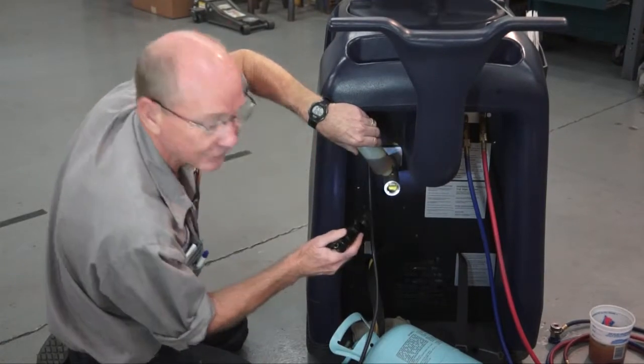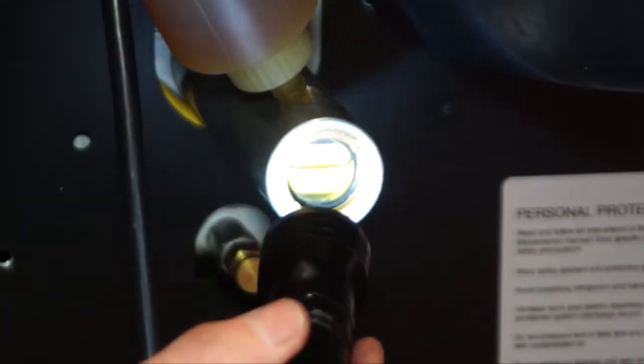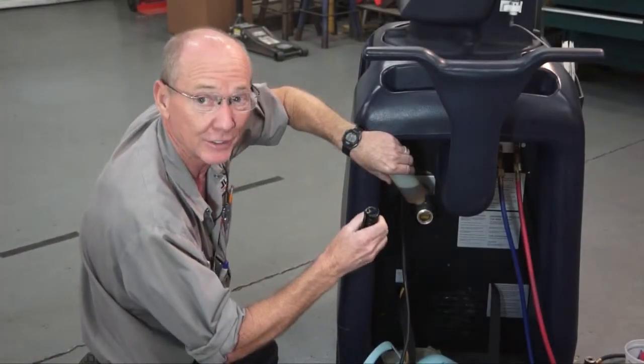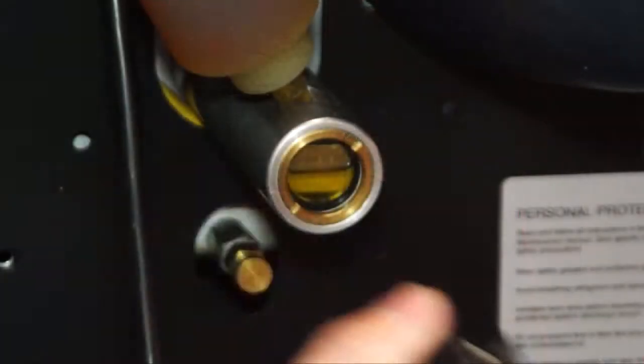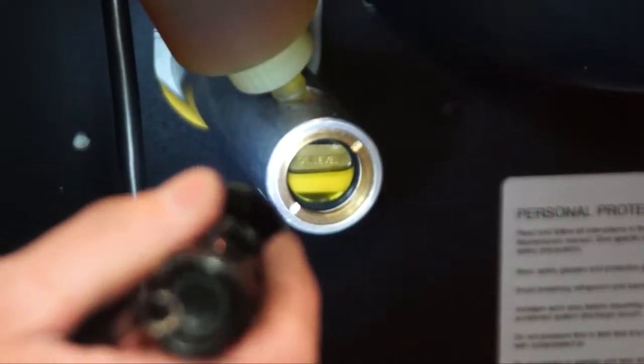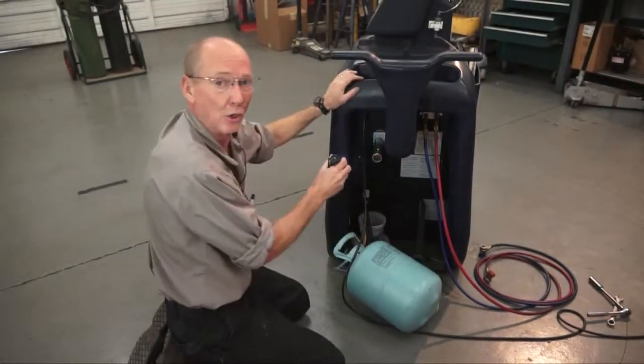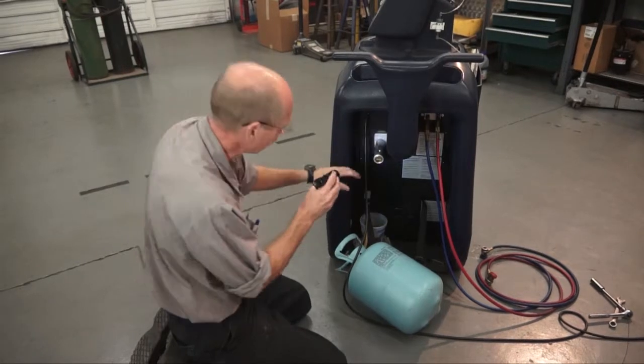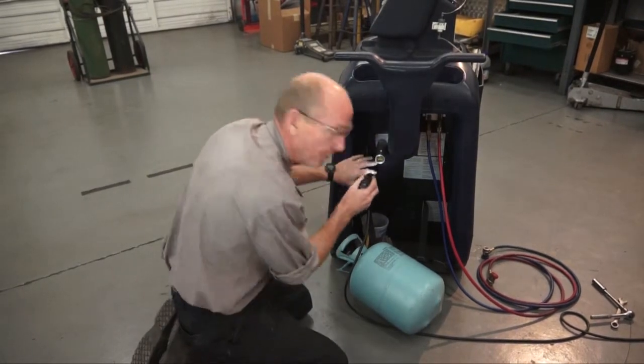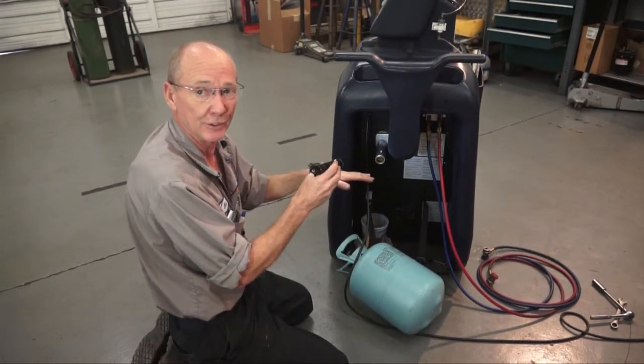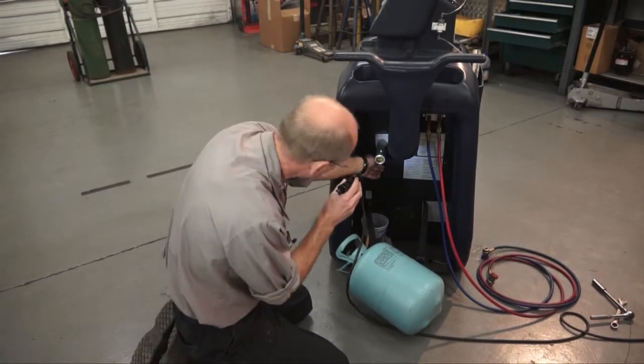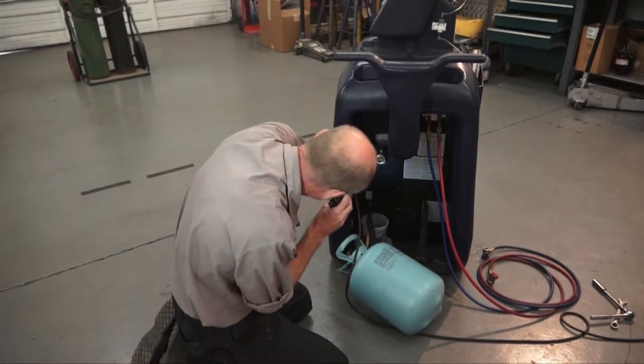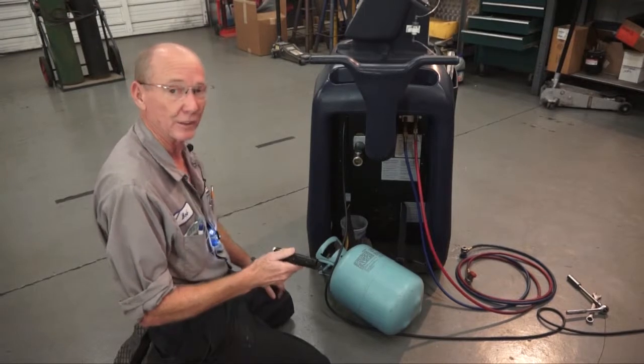Yeah, continue to add until the oil level drops down to even. If you happen to put too much oil in, then you can drain it down until the oil's even with the level indicator. I put the remainder of my oil in, but it's just maybe a 1/16 of an inch above the oil full mark on the oil level indicator. So I'm just going to drain a little bit out until it's even. It's dead even. I'm going to reinstall my cap, check the oil level again, and that should complete the service.